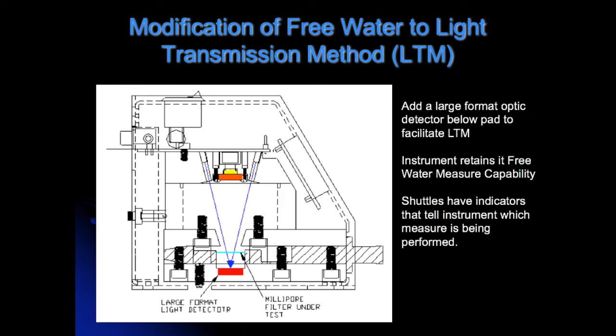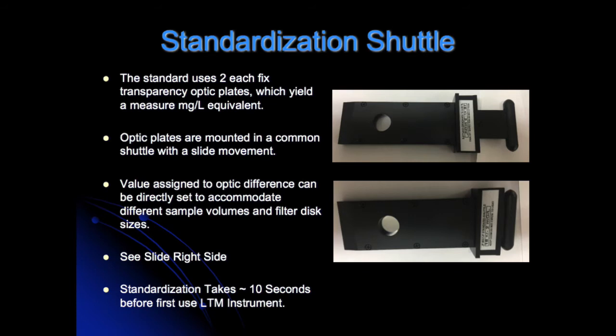This keeps the unit extremely small at only 4 inches by 4 inches on a desktop. Similar to what we did with the JFWA-1 for measuring free water and developing a standardization shuttle for verification and field calibration, we have also developed a standardization shuttle for the particulate side of the device for the light transmission method part of the instrument. The particulate standard shuttle uses two fixed transparency optic plates which yield a measured milligrams per liter equivalent. Optic plates are mounted in a common shuttle with a slide movement. The value assigned to optic difference can be directly set to accommodate different sample volumes and filter disc sizes. The slide goes in and out and it's a magnetic slide, which is how the device knows if the slide is in or out.